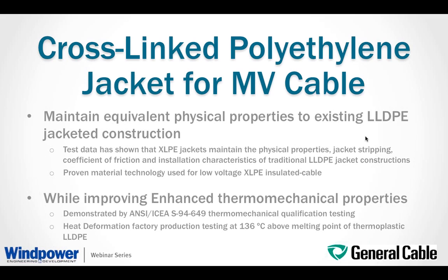Also noted, in the past XLPE materials required to be manufactured and cured on the CV line, so it was not possible to apply an XLPE jacket due to, again, the problems of passing the insulated core with its metallic shielding into the CV line. Now, with the newer, more secure XLPE material technology, it is possible to apply this kind of jacket material using the same type of extrusion line as applying an LLDPE jacket. It is also a proven technology used for many years for low voltage XLPE insulated cable.